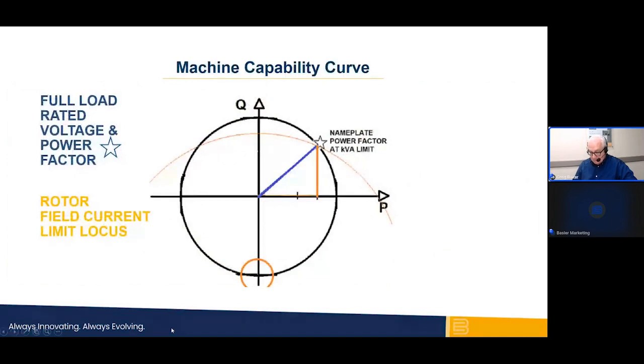The key to the field current limit is the intersection of the rated rotor current, the rated power factor, and the rated capacity. It's at the point in this diagram that I have marked with a 5-pointed star. The orange arc in my diagram here is the locus of that field current over the range of output operation of the prime mover. This arc forms a second component of the capability curve, the field current limit. Next slide, please.